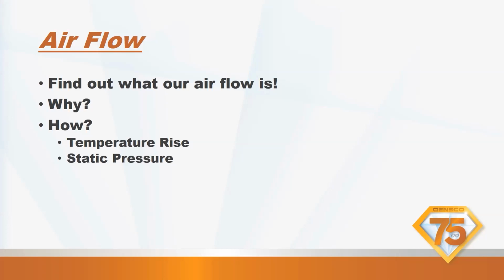If we're 10% off of what the rated is, that's the compressor killer. Okay, compressors die because we have too much airflow or not enough airflow. So if we're not verifying our airflow, we are not setting up the equipment correctly. How are we going to do that? We can take a temperature rise and do a calculation. We can take static pressure and use the pressure charts in the book.